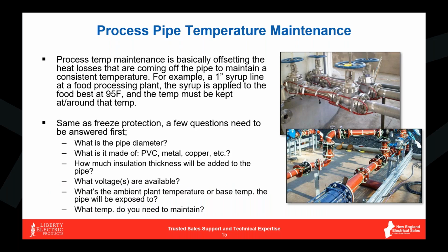Now, we don't want to be grossly over on these as well, because depending on what the material is inside of that pipe, when you're dealing with things like molasses or oil or sugars, things of that nature, we want to make sure that we're not putting too much heat on that pipe to where we can affect what's in it. So again, we're going to try and get a whole lot more spot on to what the actual loss number is.